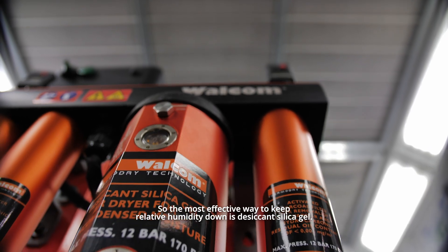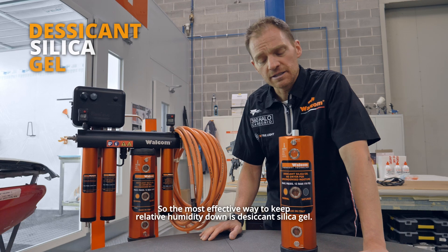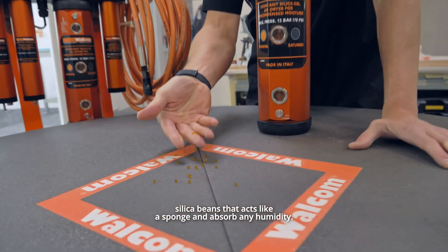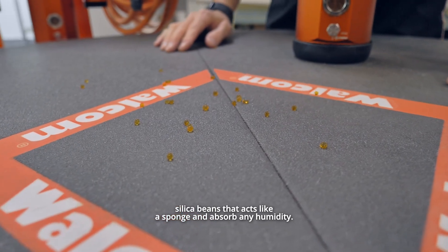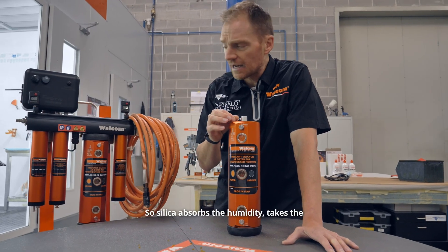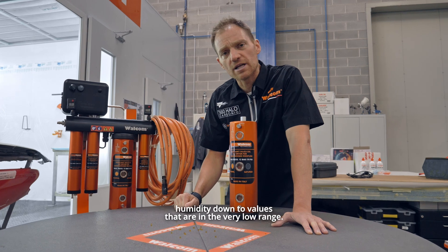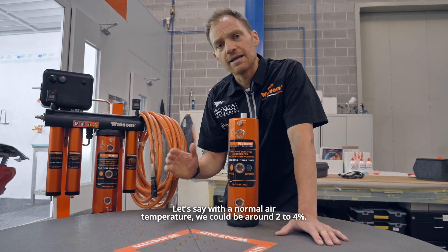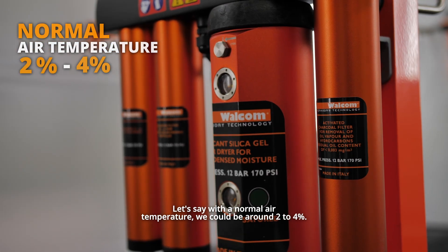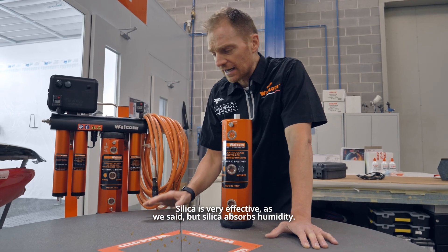The most effective way to keep relative humidity down is desiccant silica gel — simple silica beans that act like a sponge and absorb any humidity. It's very effective. Silica absorbs the humidity, taking it down to values in the very low range. With normal air temperature, we can be around 2% to 4%. With heated air, we can go even down to 0%.